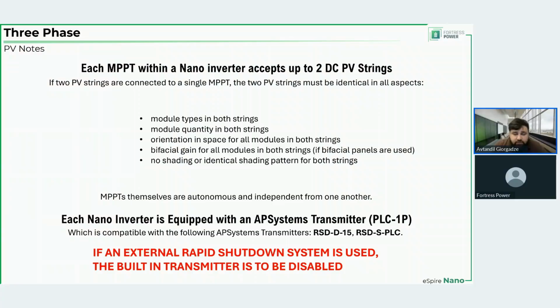If there is shading, preferably there should be no shading, but if there is shading, the shading pattern must be identical between both strings. All of this matters so that the voltages of these strings are as close as possible, right? Compared to if you had two identical strings, but one is north facing and one is east facing. They would have different voltages. They would have different maximum power points at different times. So we don't want that, and you don't want that too. That can lead to faults, curtailing, clipping, all kinds of weird things. So please, if you connect two strings to each MPPT, make them identical in all aspects. That is not to say that strings that go to different MPPTs have to be identical. Quite the contrary, they can be completely different from one another because MPPTs are autonomous. They're not directly interconnected in any way.